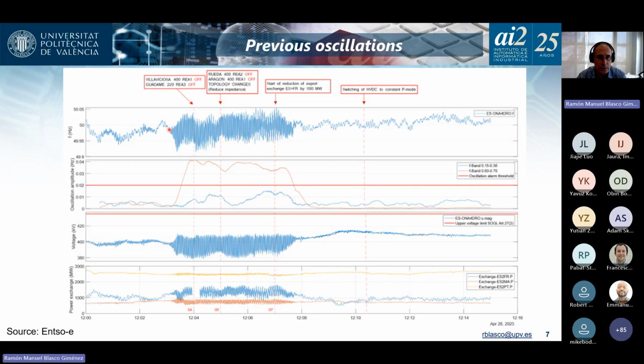Again, during these oscillations, you see that what the TSO tries to do is to switch off, in this case, the shunt reactors. So when it says the reactors are getting off, topology changes, which means connecting more lines, and reducing the exchange between Spain and France. The other action that has been found to reduce these oscillations is to switch the HVDC link to France to constant P mode, to constant power, instead of AC emulation. So all these actions contributed to reduce the oscillations, but also contributed somehow to create a situation for the increase of voltage.